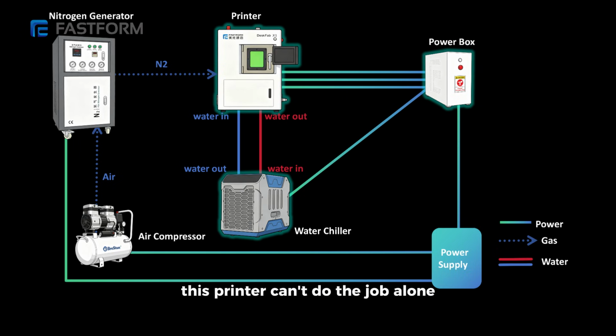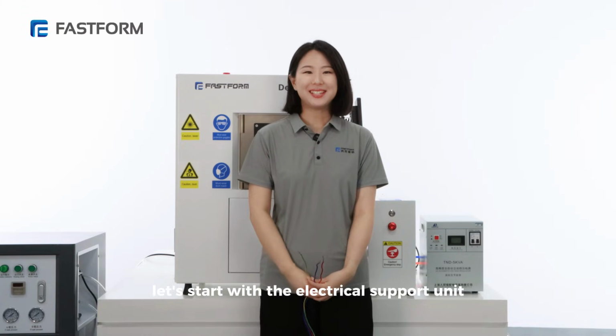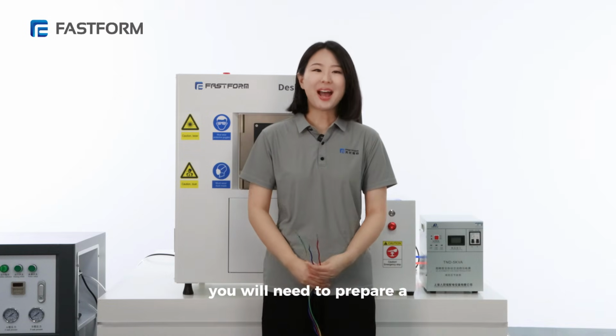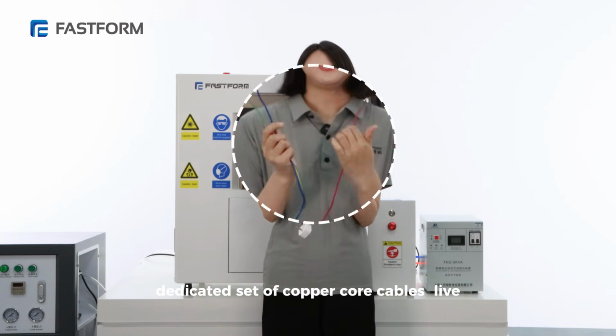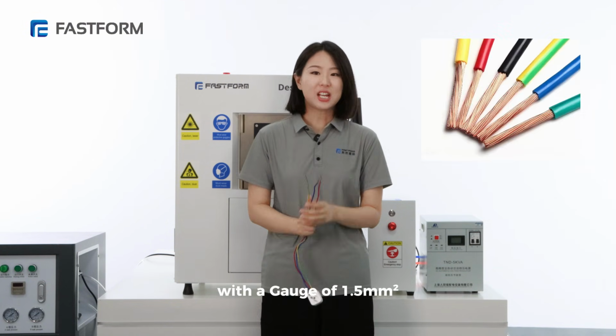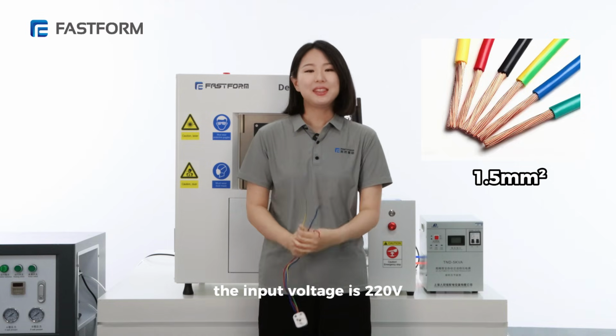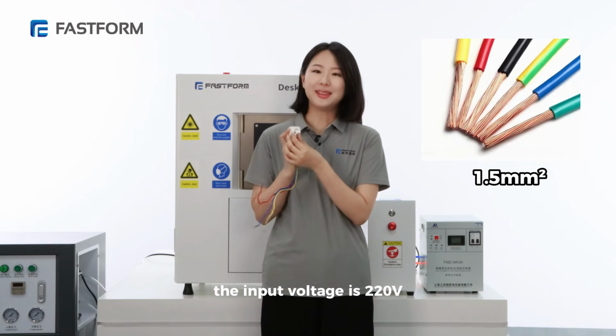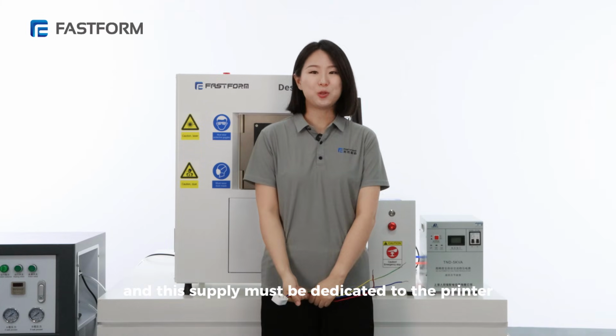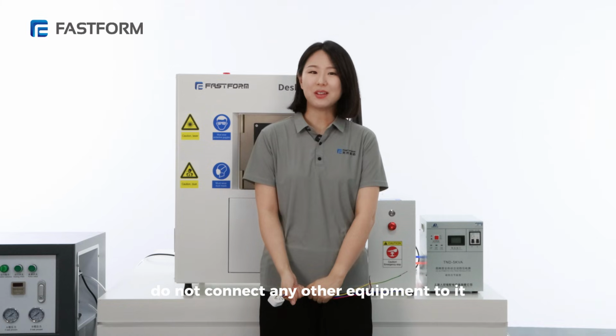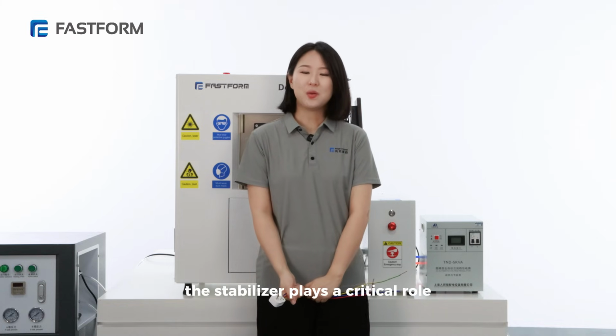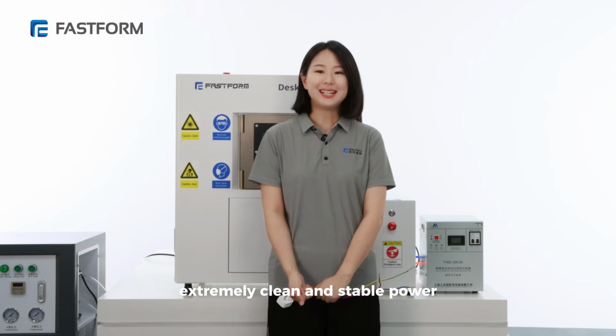Here's the thing. This printer can't do the job alone. It needs three essentials to run reliably: electricity, gas, and water. So we've designed our auxiliary systems to match, one for each. Let's start with the electrical support unit, the voltage stabilizer. You will need to prepare a dedicated set of copper core cables, live, neutral, and ground, with a gauge of 1.5 square millimeters. The input voltage is 220 volts, and this supply must be dedicated to the printer. Do not connect any other equipment to it. The stabilizer plays a critical role. The SLM system demands extremely clean and stable power.